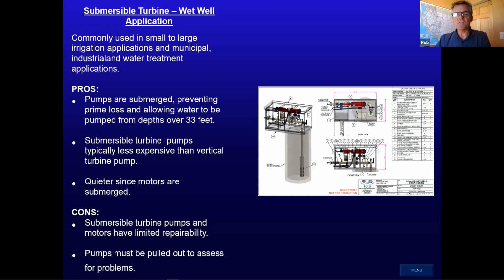Yeah, so I think one of the most important things you're going to see is where the shaft of the pump attaches to the motor. There's a transition from an area that has pressurized water in it to a motor that needs to remain dry. At that point, there's some sort of a seal, either what's known as a mechanical seal or what's called packing. To properly maintain and ensure that those are working right, there's a fair amount to that. We will be posting on our website shortly instructions for how to do that on virtually any pump anywhere. That's really important. That's one of the causes of big problems, when those shaft seals start to have problems and they're not maintained or tightened properly.